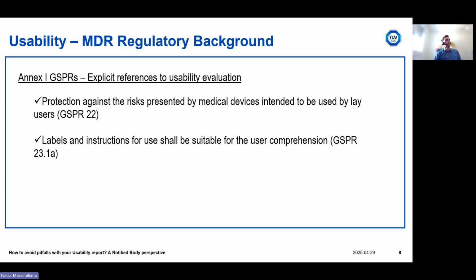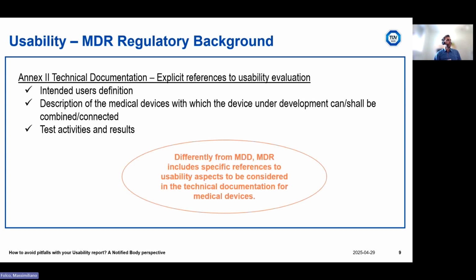There is a GSPR that is requiring a specific protection against the risks related to the lay users, so the intended users category that is called lay users, so the users that are not experienced and that probably require some kind of training, and so on. So this is just for having an idea of the fact that, differently from MDD, MDR includes specific references to usability aspects to be considered in the technical documentation for medical devices. And this is one of the bases of our technical documentation assessment that we perform for the initial certification of medical devices under MDR, and also for the MDR surveillance activities that we are actually required to perform by the European Commission, for confirming the validity of the MDR certificates after the initial release.